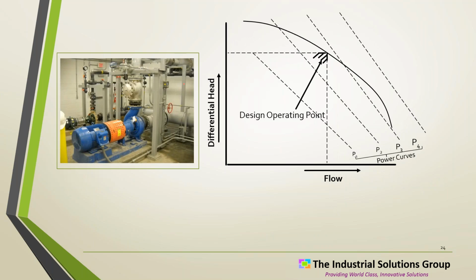And these are important questions to answer because when an engineer designs the pump, it's around this very specific point. We have the differential head. Another way of saying that would be the pressure difference across the suction and the outlet. And every pump's going to have a characteristic curve. On the x-axis, you plot flow. And it makes sense: the more you flow, the lower the pressure. This is the capacity, the performance curve of the pump. And the point here marked with a little angle is the design point. So the engineer wanted that amount of flow at that pressure drop in order to assure that all of the equipment downstream was getting the proper amount of flow.